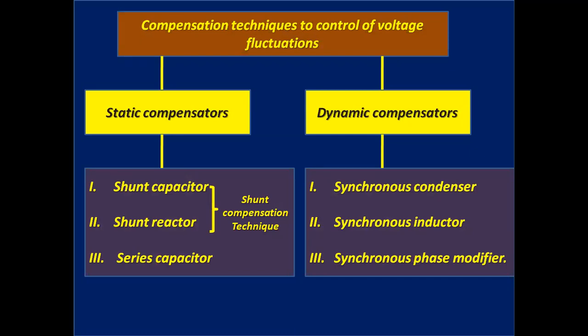Say, compensation techniques to control voltage fluctuations. One is static compensation, another is dynamic compensation, or static compensators and dynamic compensators. Static compensators are the shunt capacitor, shunt reactor, and series capacitor. Dynamic compensators are the synchronous condenser, synchronous inductor, and synchronous phase modifier.